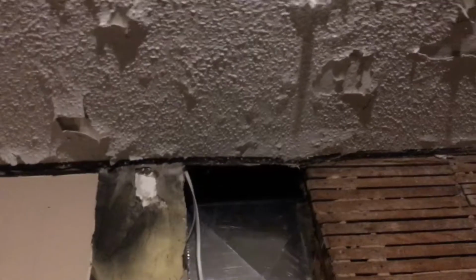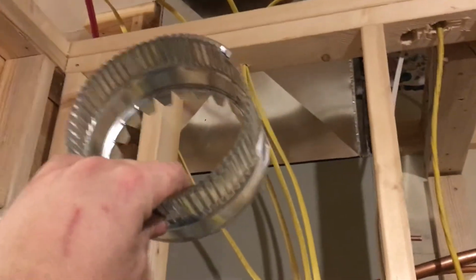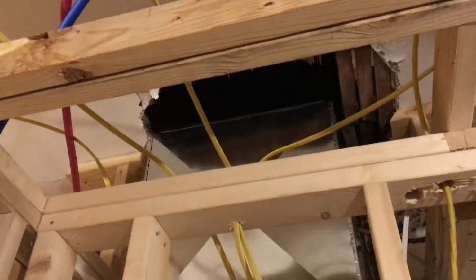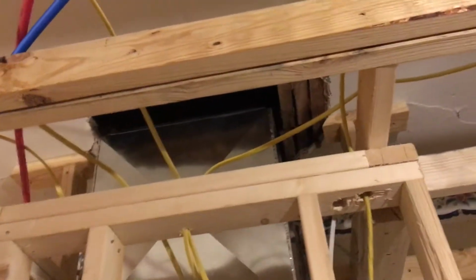I went ahead and set the plenum up there just to see how it fits. It just fits, and it's wide open to the attic up there, so I can cut my 2 holes for my 8-inch takeoffs and put those in right in the very top, going straight up into the attic. And then over here I can cut my 2 holes for my 6-inch takeoffs for the kitchen and bathroom right there on the side. That should be good to go.